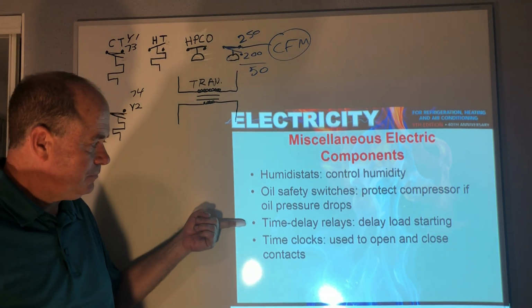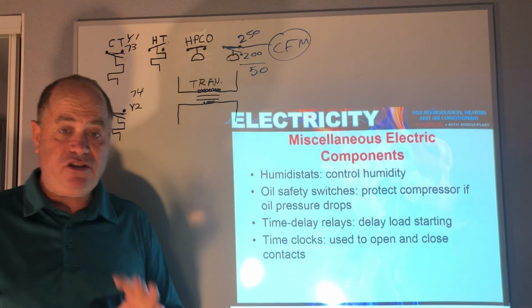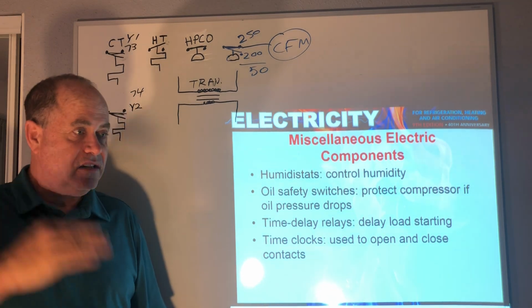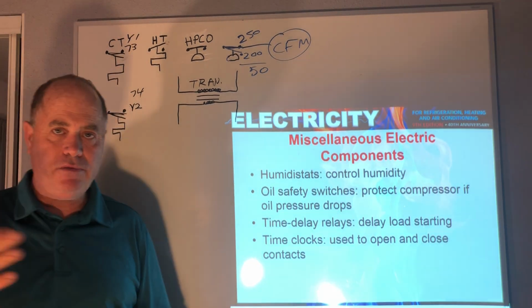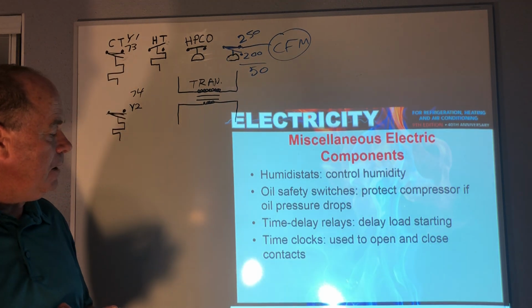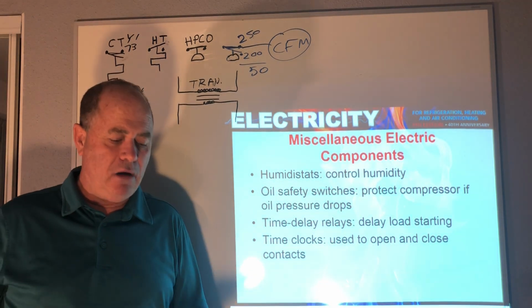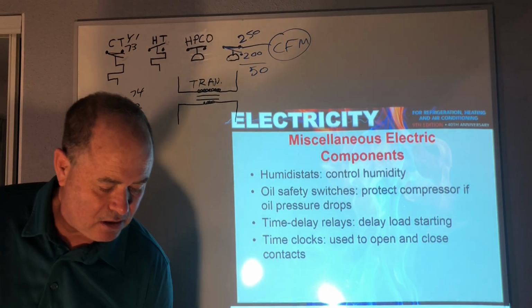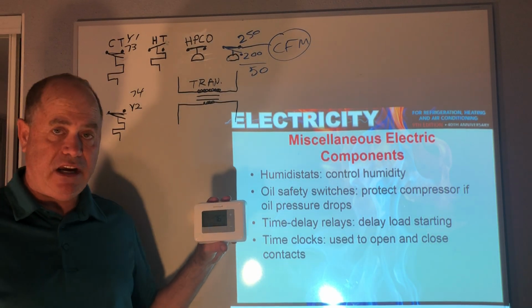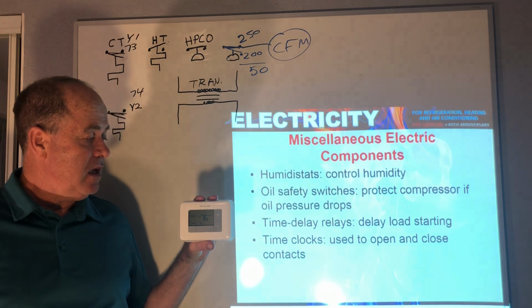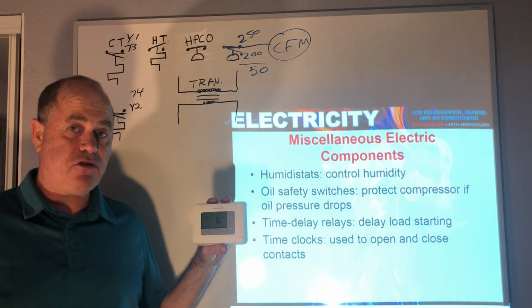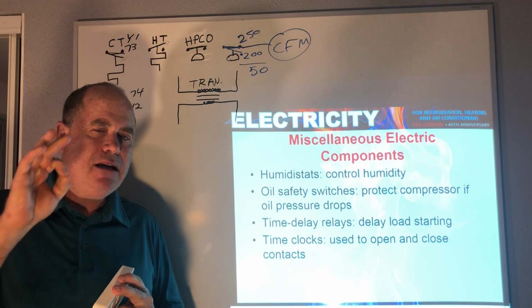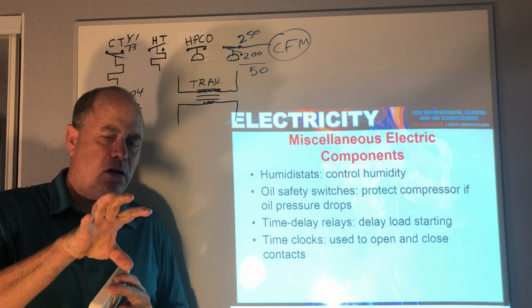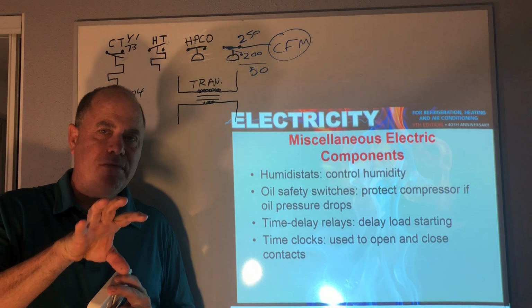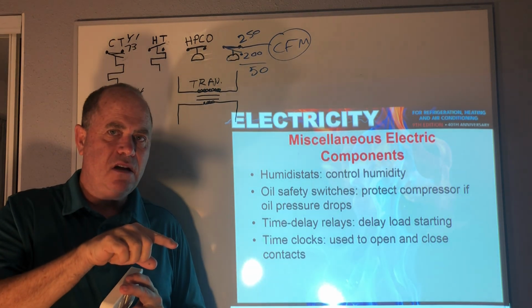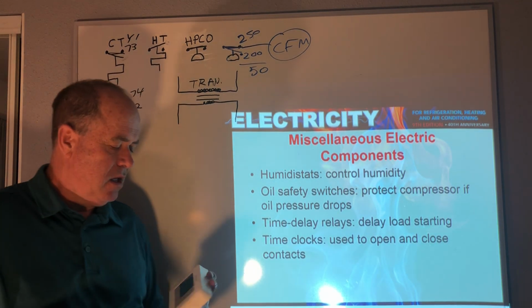We also have time delays. Back in the past, I used to install little time delay relays on systems that would short cycle. People would fight over the thermostat or whatever. But almost all modern thermostats now have a delay on break and will not let the compressor restart for another 3 minutes. In fact, some of the very newest small thermostats for refrigerated boxes also have that technology now.